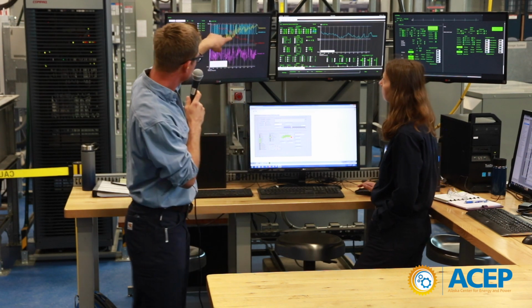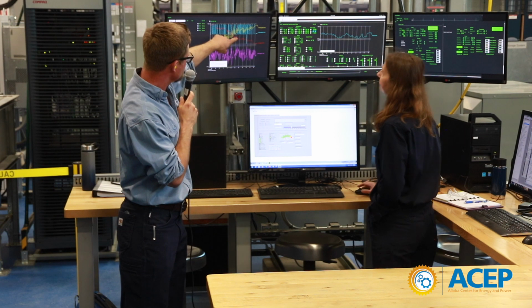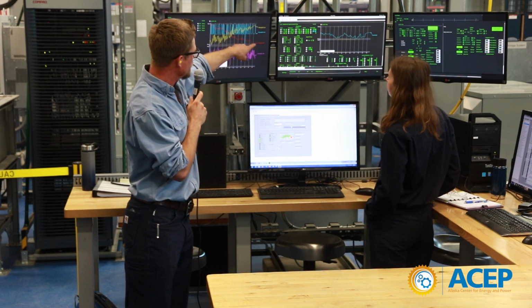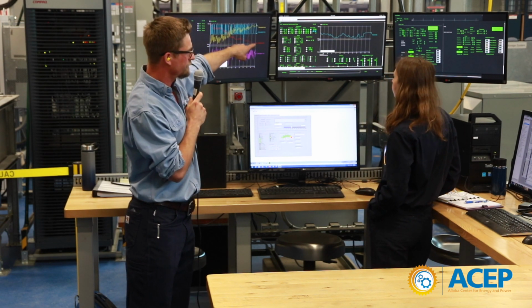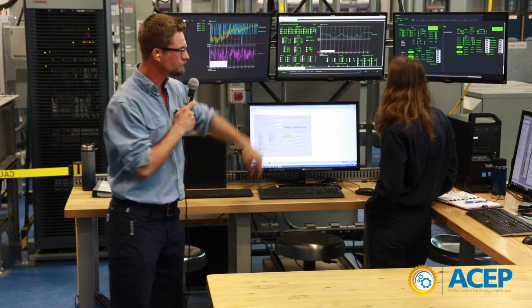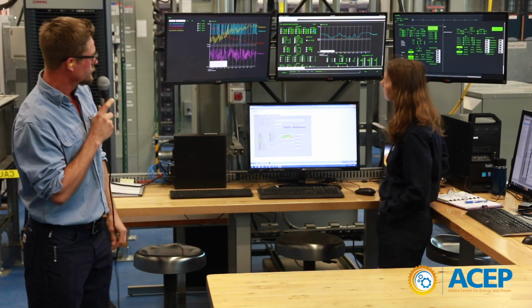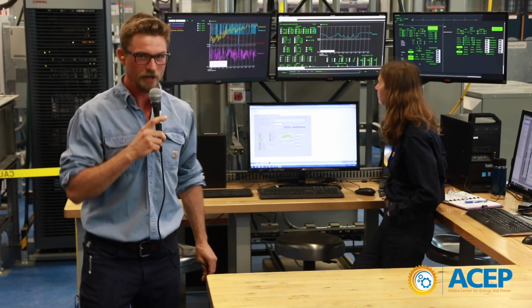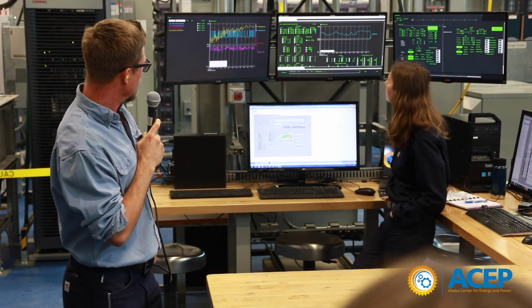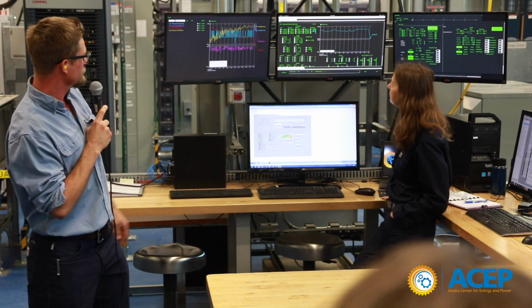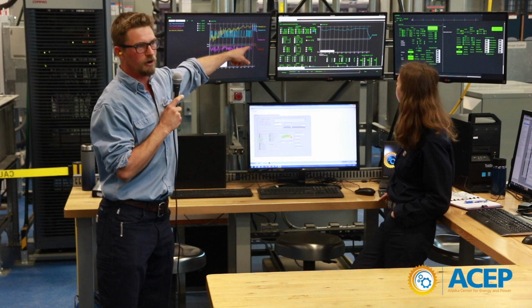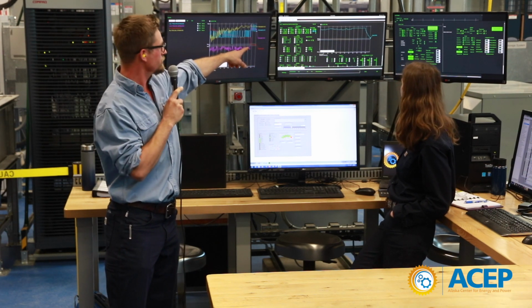You can see the red line here, this is our diesel generator. Now we have 19.5 kilowatts on it. Dave, our power plant operator, is going to open up the circuit breaker. What just happened? Red zero — our generator is not doing anything right now.